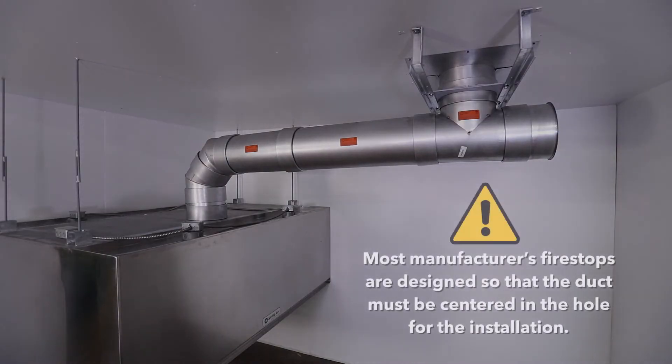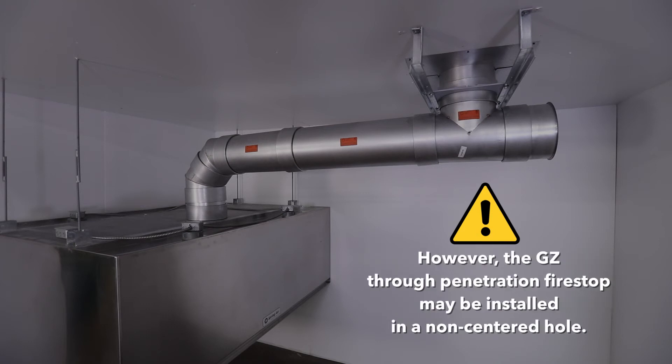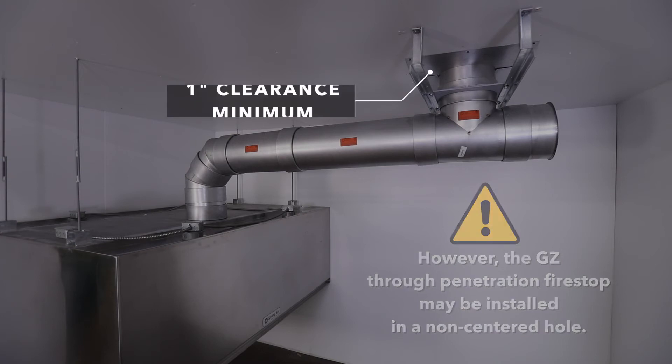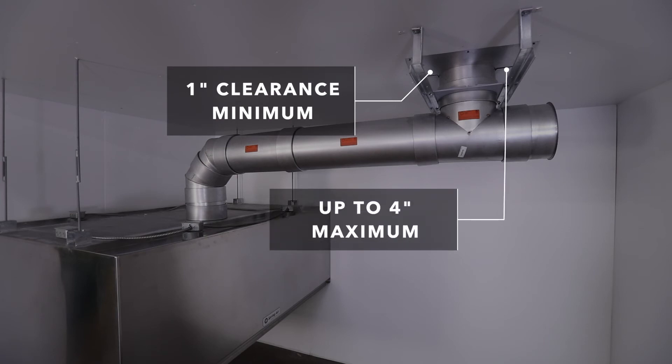Most manufacturer's firestops are designed so that the duct must be centered in the hole for installation. However, the GZ through penetration fire stop may be installed in a non-centered hole with clearance as little as one inch on one side and as much as four inches on the other, or anywhere in between.